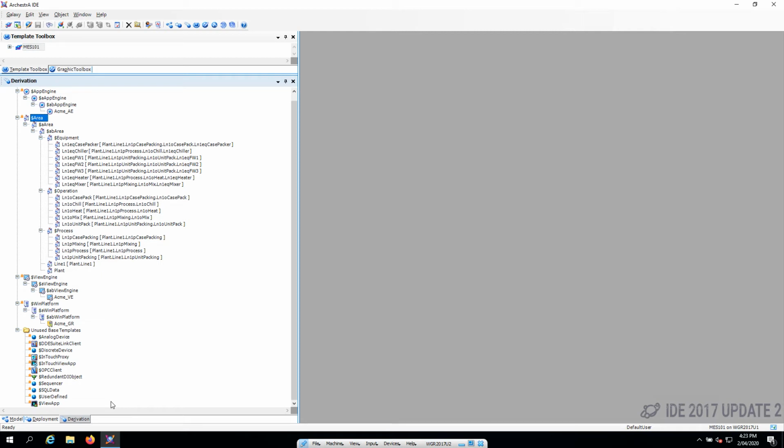So if you've got an over torque and an over temperature, and they're all based on the same motor, you're not going to want to group those together. You're just going to look at that motor and go, okay, motor one's got a problem. You might drill into it and look at those tags later, but you're not going to aggregate those up and then want to see those at a higher level. That's just a level of detail that you don't need. In your application, you might want to go 5, 6, 7 layers deep, but for us, we're not going to at this point.